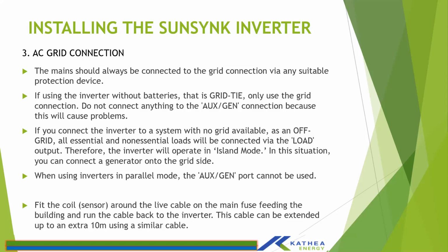Just on that point, we've got an application where we might have a complete off-grid scenario like you're explaining now. We definitely want to make use of a generator if we had a couple of cloudy days and the battery can't hold the loads anymore. Does the inverter give you the functionality to start the generator at a certain point, or how will that control work? Because you don't want the generator running all the time with the auto changeover, you just want it to kick in when the battery, for instance, gets to 20% or 10%. Is there a functionality that the inverter can do that for you or not?